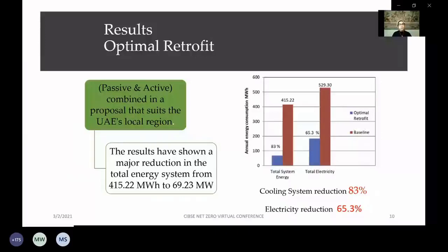Before starting the PV installation or assessing the PV energy supply, we need to include the result of the previous study done by Al-Awadi. This study shows that lighting electricity could be reduced by 25% if daylight sensors and a dimming system were provided. Thus, the total electricity consumption after considering all the retrofit actions is equal to 169 megawatt hours. So the demand is 169, and this needs to be supplied by PV panels.